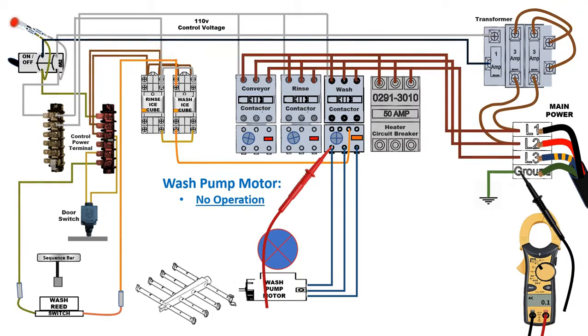Next, we're going to test voltage coming out of the contactor. Here we're showing that the contactor is not engaged and there is no voltage coming through. Our next step is that we're going to check for low voltage coming into the contactor that activates the magnet to make the contactor close its circuit. Here we have contact coming in.